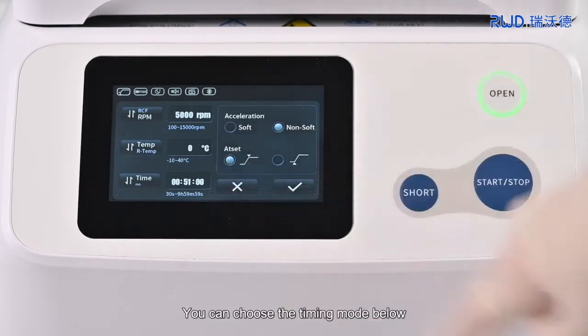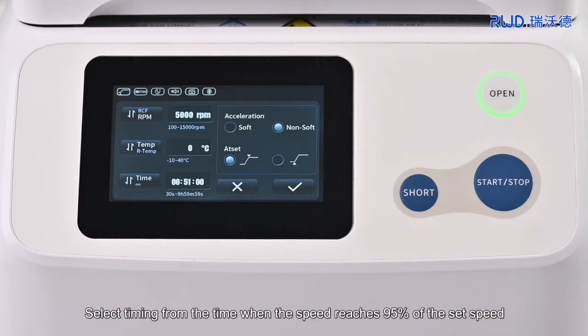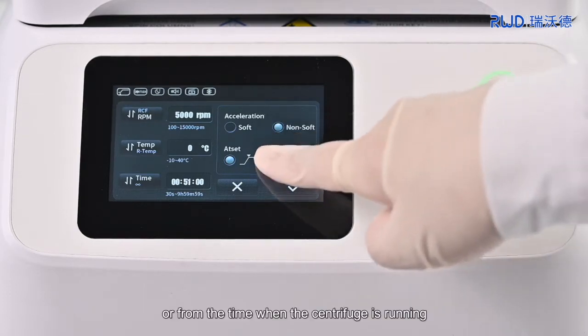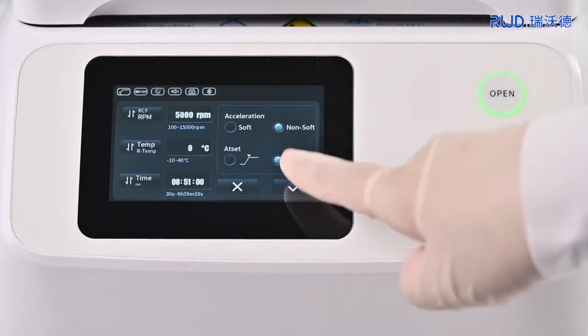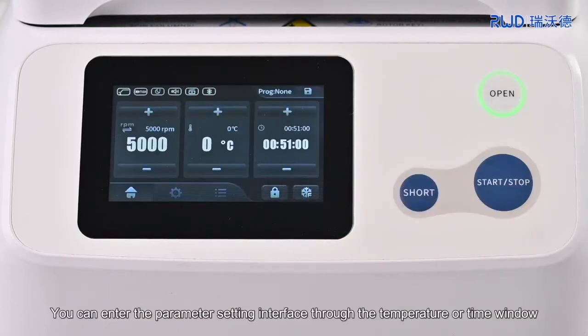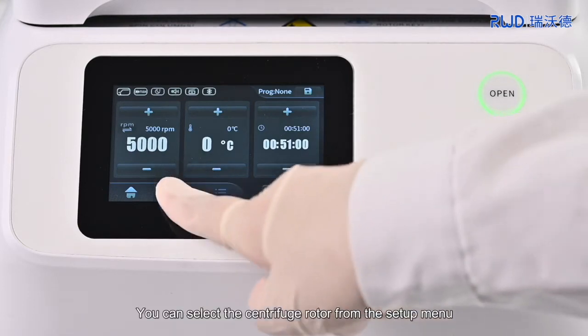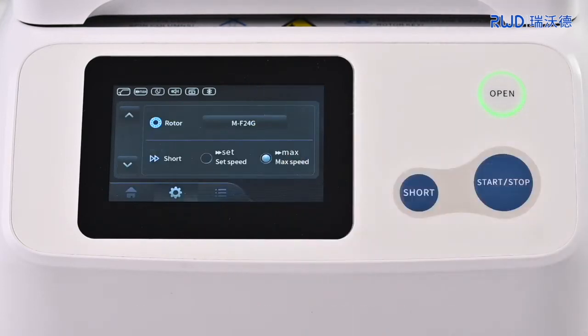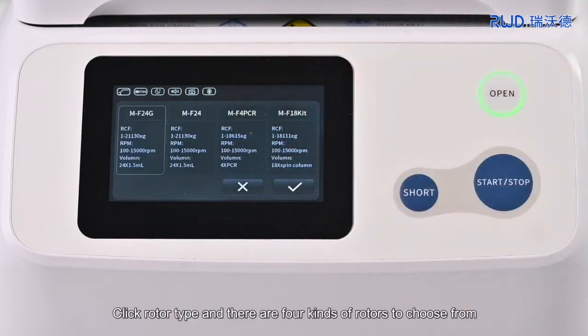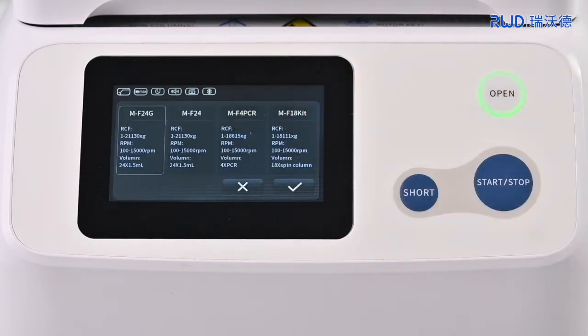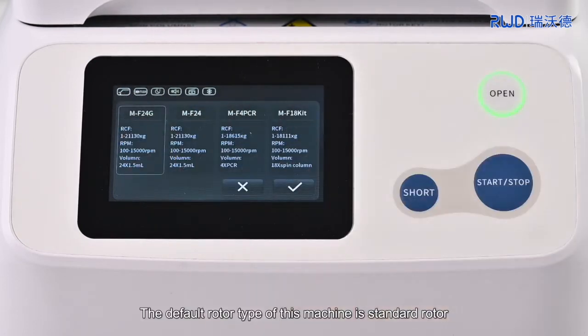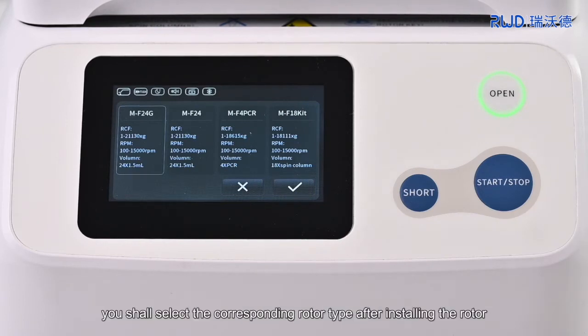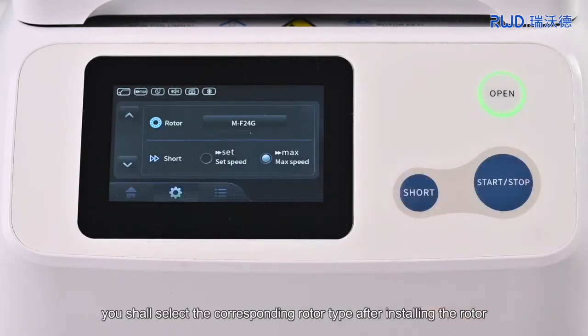You can choose the timing mode below. Select timing from the time when the speed reaches 95% of the set speed, or from the time when the centrifuge is running. You can enter the parameter setting interface through the temperature or time window. You can select the centrifuge rotor from the setup menu. Click rotor type and there are 4 kinds of rotors to choose from. The default rotor type of this machine is standard rotor. If you choose another rotor, you shall select the corresponding rotor type after installing the rotor.